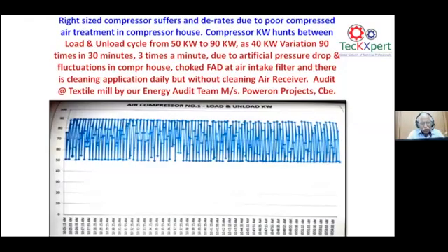You have seen many of the areas where we have done the energy audit. We could find this type of fluctuations, especially happening in the compressors. It's a cyclic fluctuation happening three times a minute, from 50 kilowatt to 90 kilowatt. You can see the acid test this gives to your electrical distribution system, and how the compressor is performing. The compressor's health also deteriorates very badly if it is fluctuating like this. The reason is a very choked air intake filter.